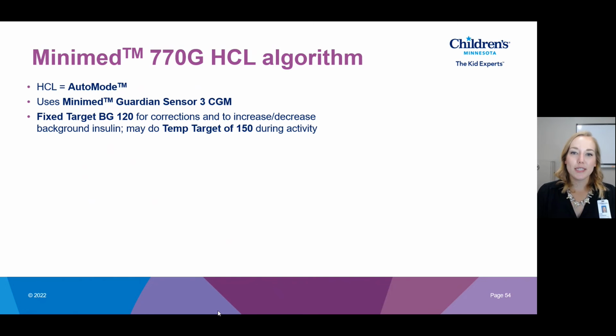For the algorithm, it is using a fixed blood sugar target of 120 to make dosing decisions. The pump will be increasing and decreasing insulin in the background automatically every 5 minutes based on that sensor value and trend arrow. And then it's looking back on your insulin use history to make decisions. It's not using your basal rate to make decisions. It's actually going off of your true pump history. You can change the target to 150 temporarily for activity. That way it's trying to get you to stay at 150 versus at 120, which can help prevent hypoglycemia during activity.